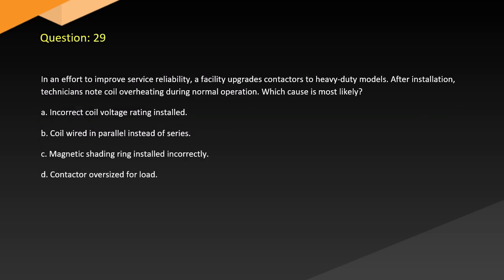Question 29. In an effort to improve service reliability, a facility upgrades contactors to heavy-duty models. After installation, technicians note coil overheating during normal operation. Which cause is most likely? A. Incorrect coil voltage rating installed. B. Coil wired in parallel instead of series. C. Magnetic shading ring installed incorrectly. D. Contactor oversized for load.